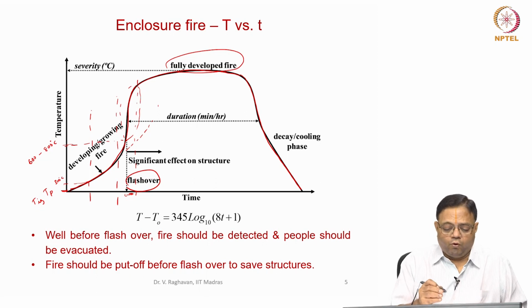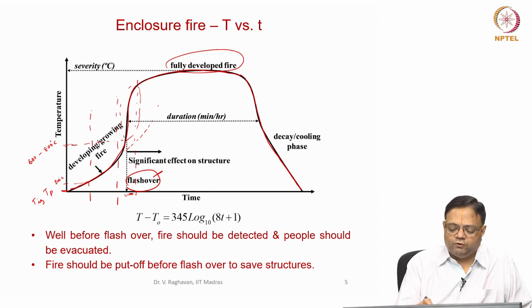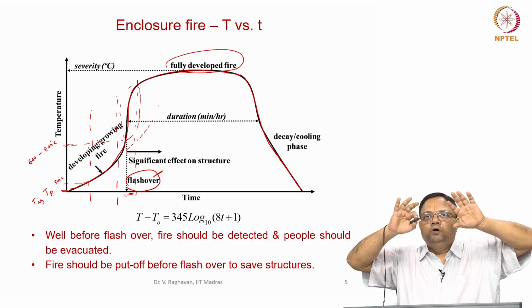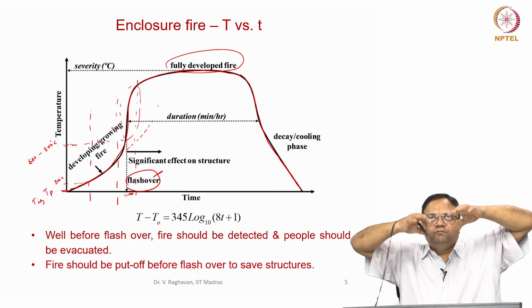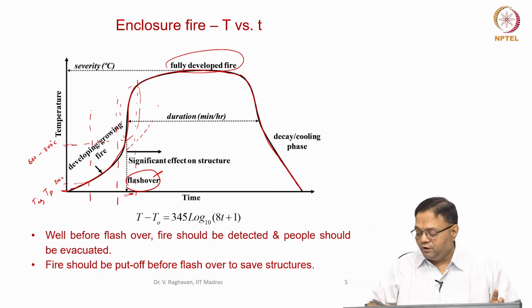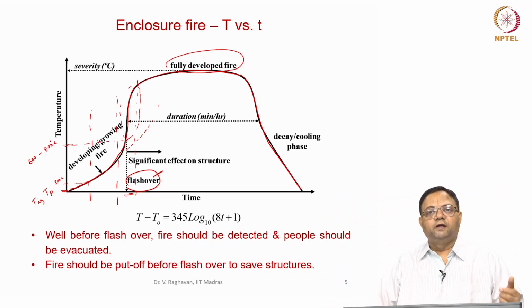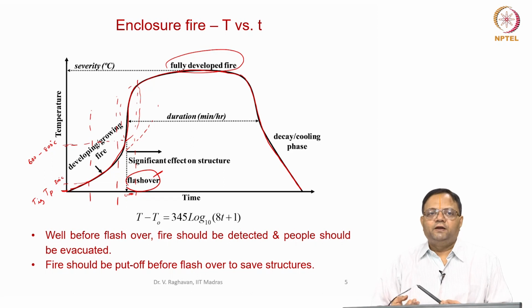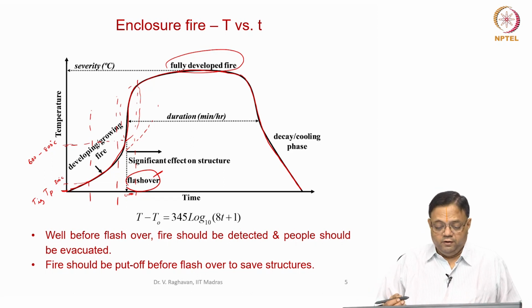The flashover condition is very tough to determine. So, you can say that if the smoke layer, the hot gases which are accumulating over the ceiling, reaches around 800 degrees or 600 to 800 degrees, flashover can occur. So, that is the condition, but it may vary based on the situation.